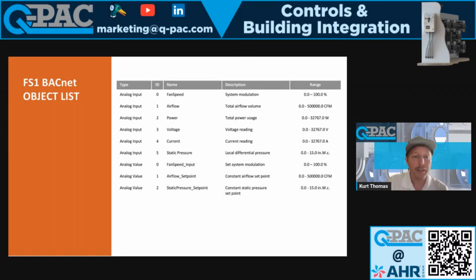So our BACnet list, we provide quite a lot of information. The fan speed. So this is an actual feedback. This isn't saying, this is what you're telling us to run. This is actually what the fans are running at. Analog input, so the amount of airflow. So like I mentioned earlier, we do have a pressure transducer in our quick connect box, and it measures the differential pressure between the velocity pressure at the throat of the fan versus the upstream pressure. And then we can use some of Bernoulli's equations to calculate the airflow. And we pass that information along through analog input 1.